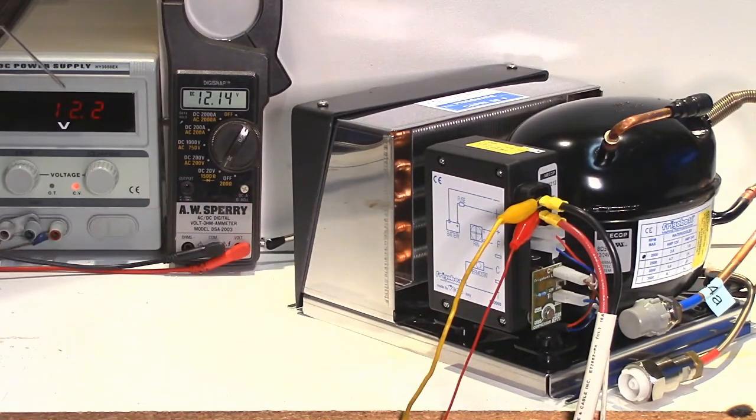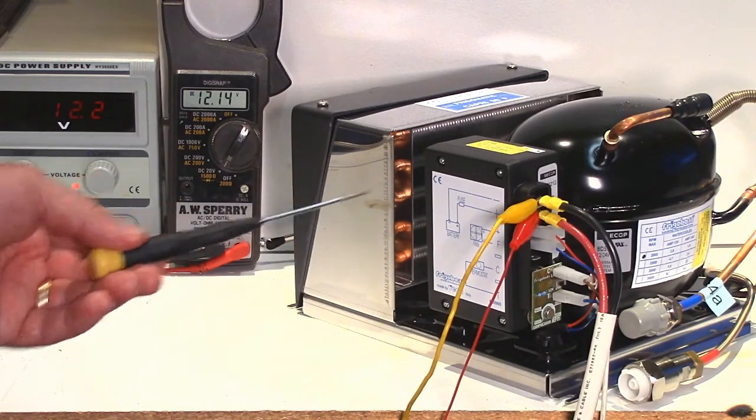So it's very important that you measure and monitor that voltage right at the terminals on the compressor no matter what the voltage says on your meter. As you can see there, there's another good illustration. Down below 10 volts, shuts off and immediately comes back up again. So if you monitor it at any other time than when the compressor tries to start, then you will see good voltage.